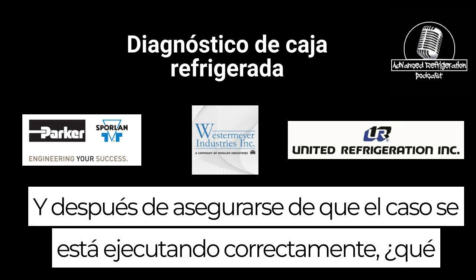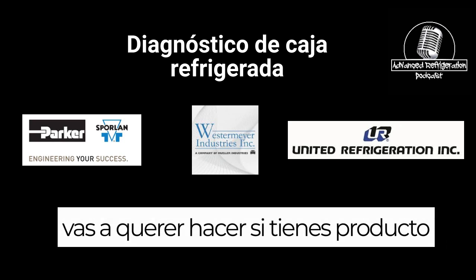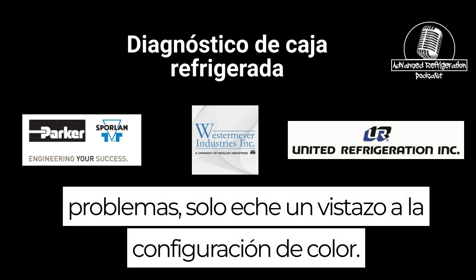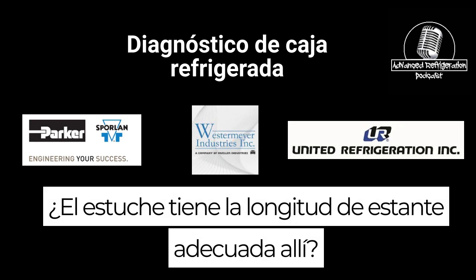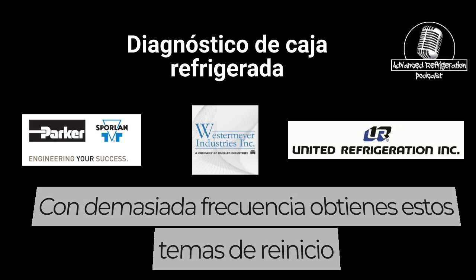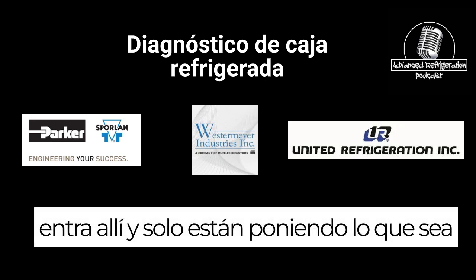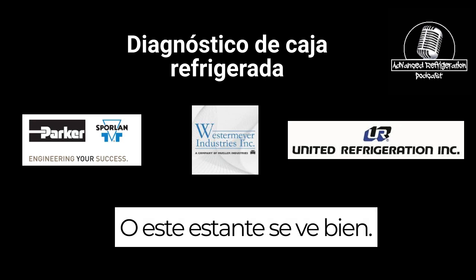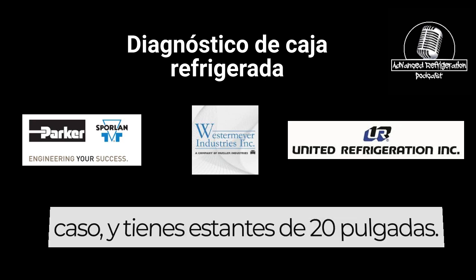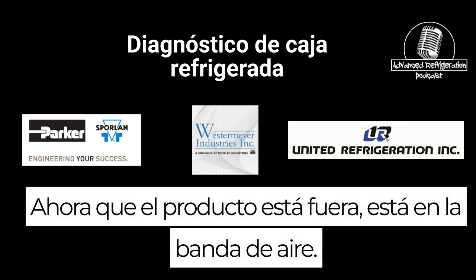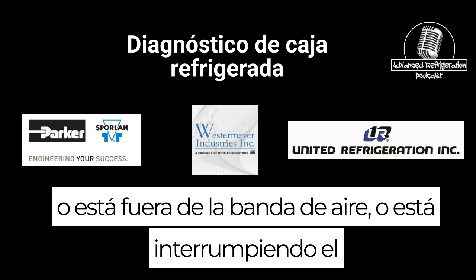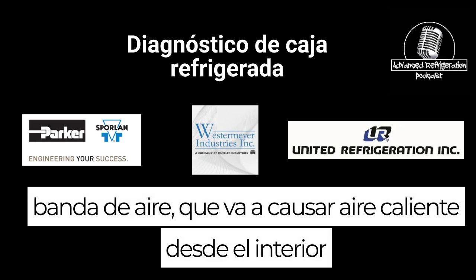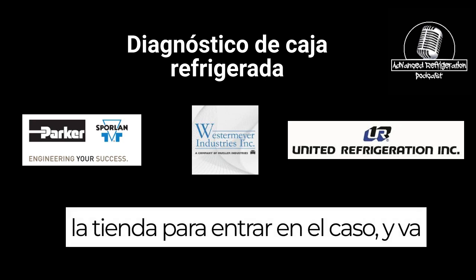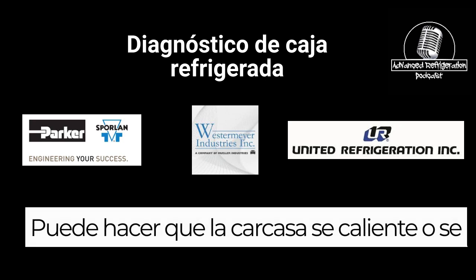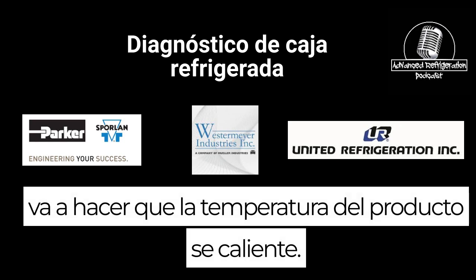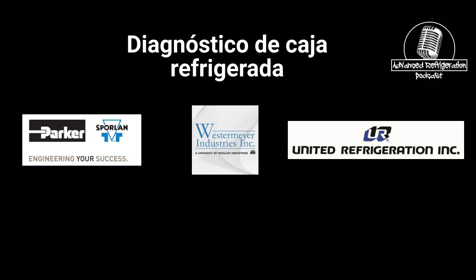And after you make sure the case is running properly, if you have product temp issues, take a look at the case, how it's set up. Does the case have the proper shelf length in there? You can find that in the manual. I see all too often these reset teams come in and they're just putting whatever shelves they find in the case, or this shelf looks good. It may require 17-inch shelves in the case, and you've got 20-inch shelves. Now that product is out of the air band, or it's disrupting the air band, which is going to cause warm air from inside the store to come inside the case. It may cause the case to run warm, or cause the product temp to be warm. One thing to be mindful of: do you have the correct shelves?